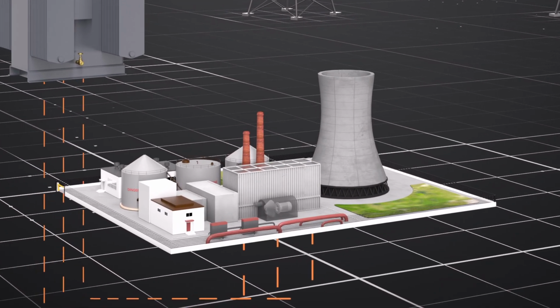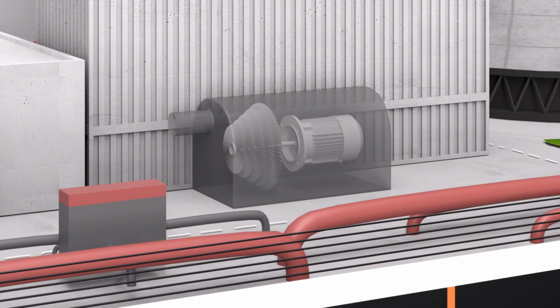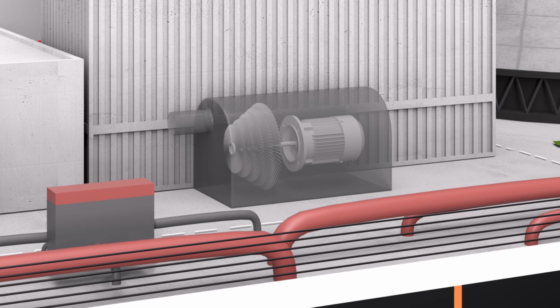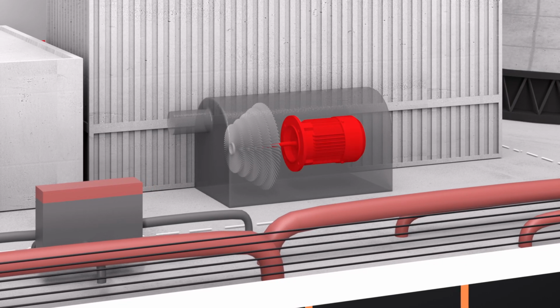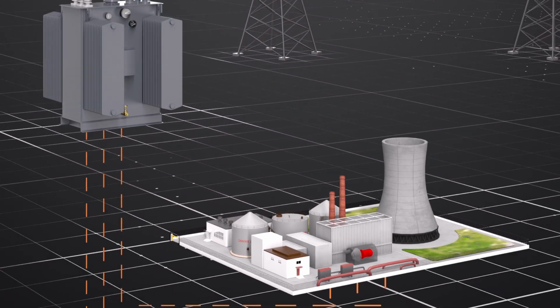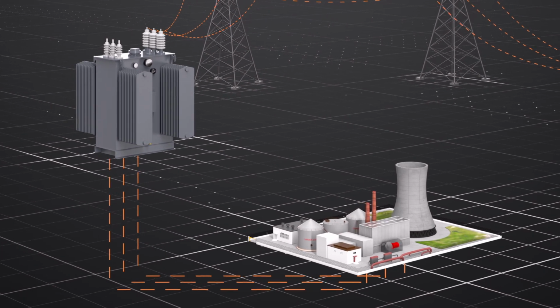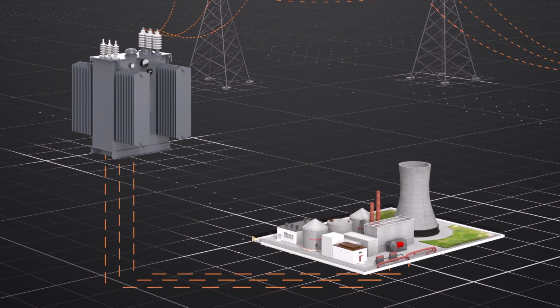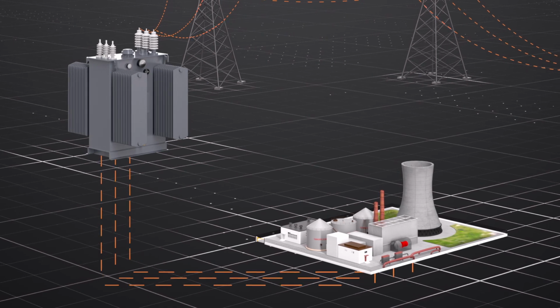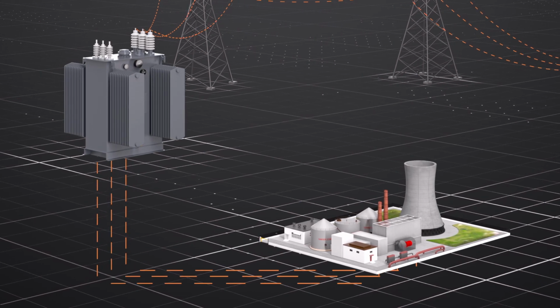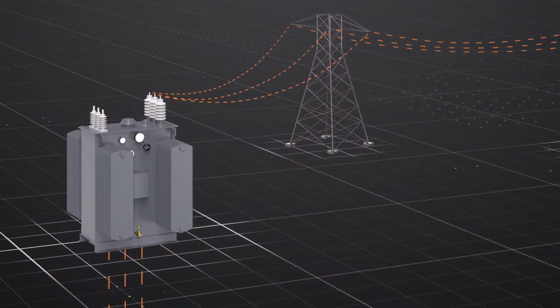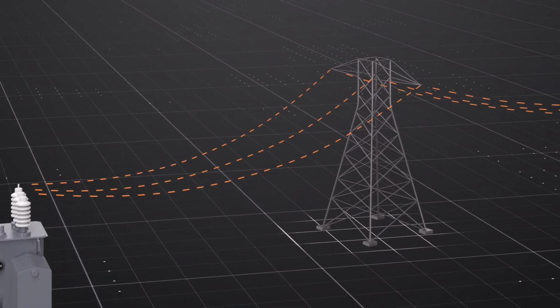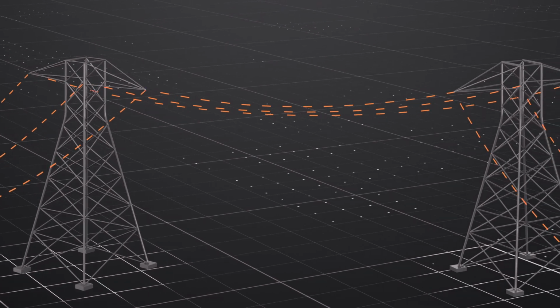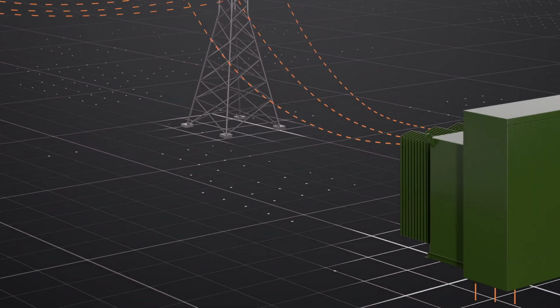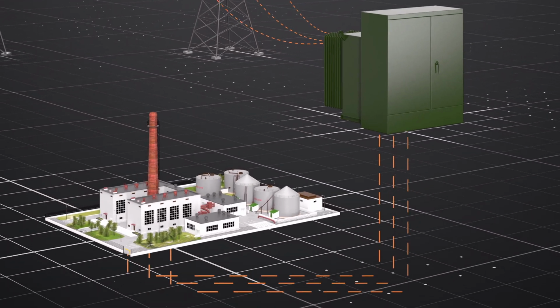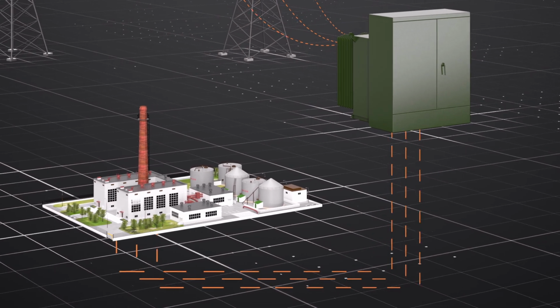This thermal energy plant uses steam to spin a turbine connected to a generator to translate the mechanical energy from the spinning turbine into electrical energy. The process produces large amounts of electricity, but at relatively low voltage. So the power must be transformed to high voltage for transmission. Every power plant has at least one step-up transformer, which boosts the voltage to get the power across long distances. As it arrives at its destination, the power must be transformed back to low voltage for use by another transformer.